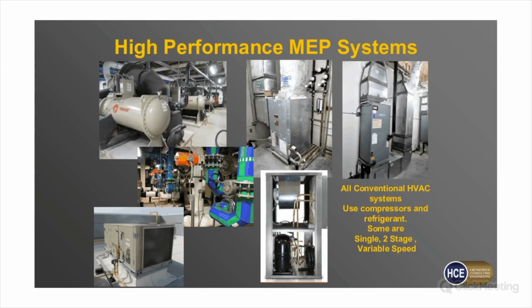Some of our clients are a one-room school, and that's the whole district - the custodian and the superintendent are sometimes the same person. So for that district everything has to be very straightforward: traditional split systems, something a residential AC tech could fix, because there are no commercial techs within 60 or 70 miles of town. But then you move up to a district with 5 or 6 high school campuses and 30 or 40 elementaries, and they have techs that can work on everything. So you really got to talk to the district or owner and see what they're comfortable with, because what they're qualified to keep running best is what's really going to give them the best efficiency.